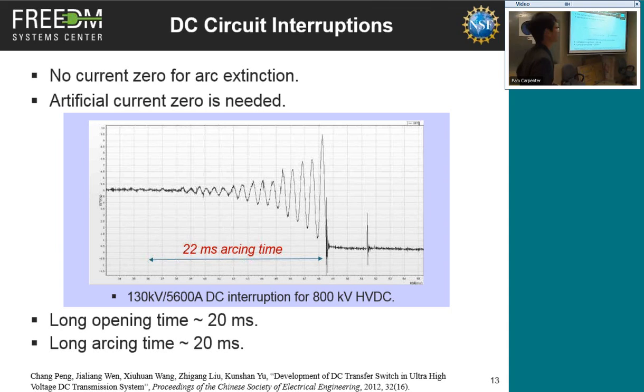So let's look at how much time is needed for this. First of all, you still need to open the contact. That's the time before the initial contact opening. That takes 20 milliseconds. On the other hand, this is the arcing time. The arc is burning in the circuit breaker chamber. So that takes about 20 milliseconds. In total, that's 40 milliseconds. Okay, this is for the DC transfer switch. It is used in HVDC transmission based on line commutated converters, not voltage source converters. So that's a different topology, and the purpose is also different. But we are talking about DC circuit breakers here.